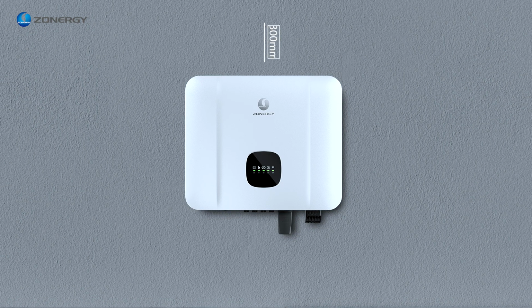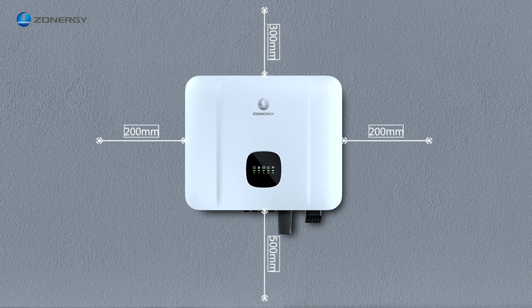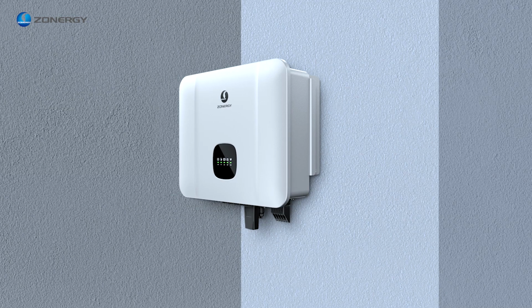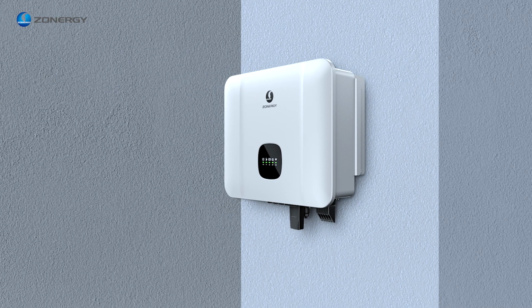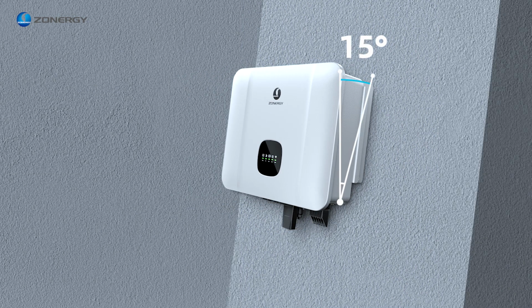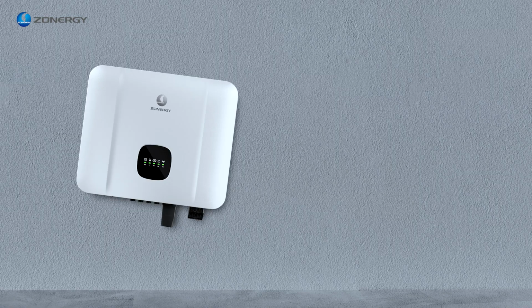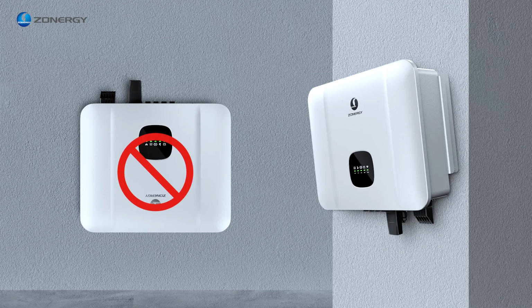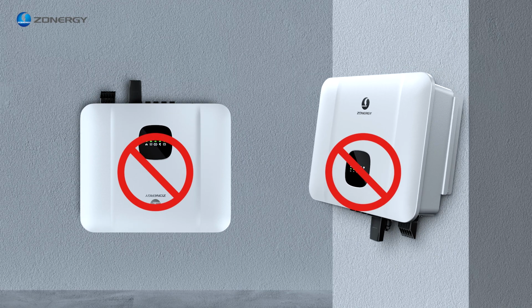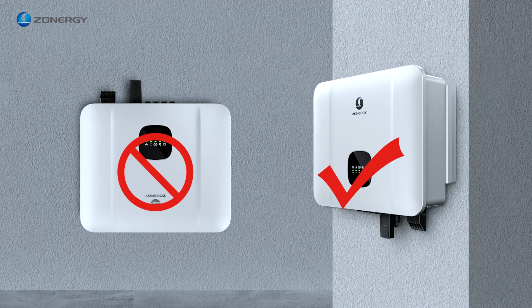The minimum upper clearance is 300 millimeters, the lower clearance is 500 millimeters, and the two sides clearance is 200 millimeters. Recommended inverter installation angle: vertical or backward less than or equal to 15 degrees. Do not invert, tilt forward, tilt backward beyond the angle, or horizontally install the inverter.